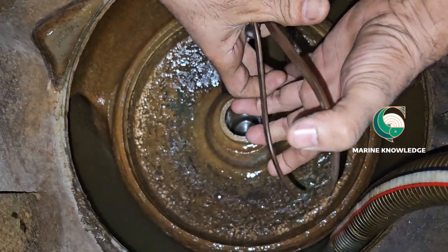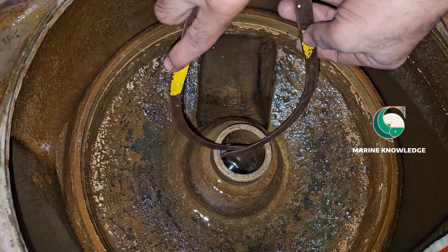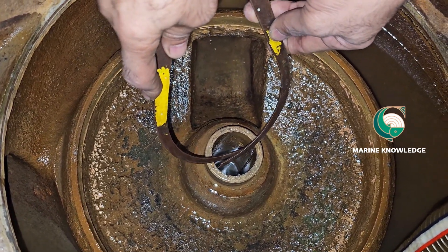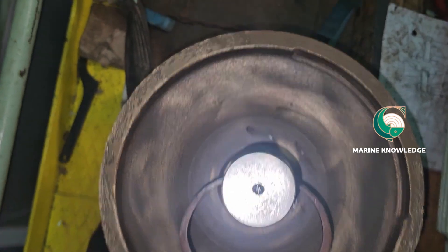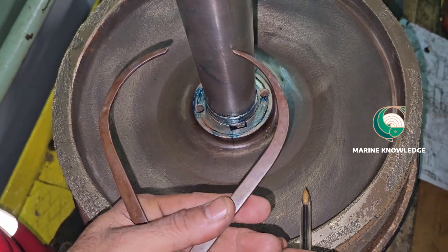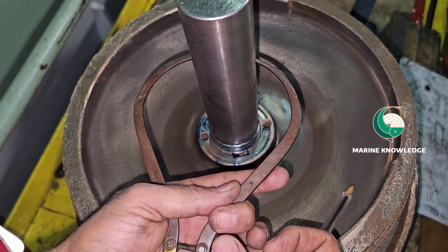Next, you need to get the clearance between the shaft and the shaft sleeve. Again, with the help of an inner gauge, take the clearance at the casing where the shaft sits. If this bush gets worn out, it will give a lot of vibration when the pump is running — that is the main reason why we need to take this clearance. Note it down: shaft sleeve inner diameter is 48 mm. Then take the measurement of the pump shaft. Subtract the two values — that is the clearance for the shaft sleeve on the shaft.